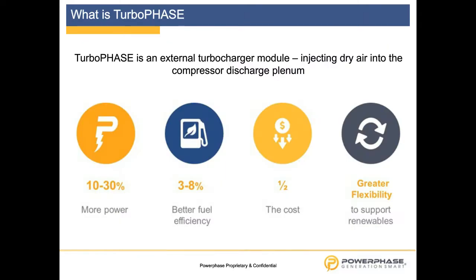A simple introduction is that the Turbophase module is an external turbocharger that is connected to the compressor discharge section of any gas turbine, injecting dry air into this plenum. With that, depending on the size and frame of the gas turbine, we are introducing a 10 to 30% power increase. We are able to increase the fuel efficiency by 3 to 8%. We are competitive in pricing compared to upgrades on new installations, and we provide great flexibility with a focus on new renewables like wind or solar.